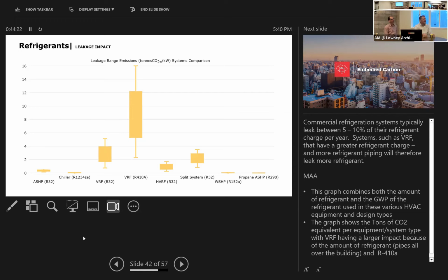Genentech, they're owned by a company called Roche, and they've got European standards, so they don't allow any hydrofluorocarbon-based refrigerants at all. At Genentech, you can use ammonia as a refrigerant, CO2, propane, and it looks like they're going to go down to CO2.